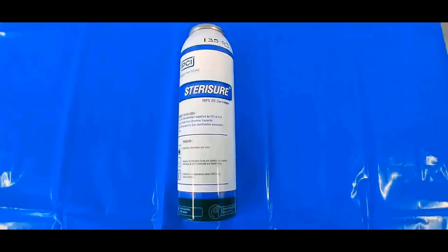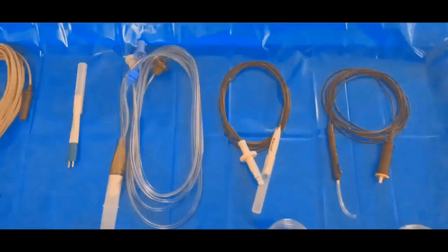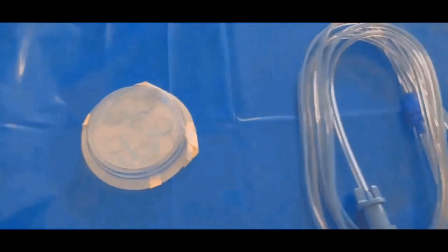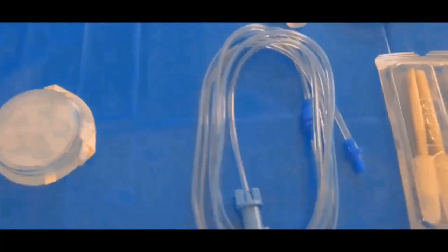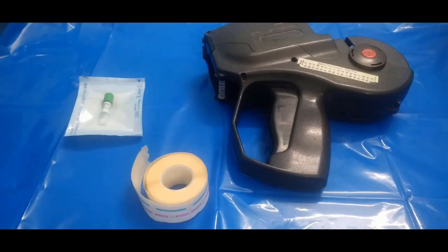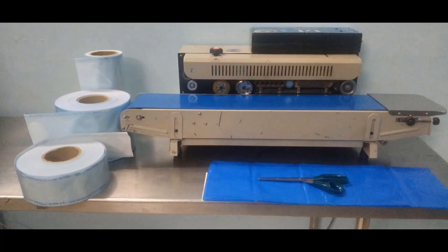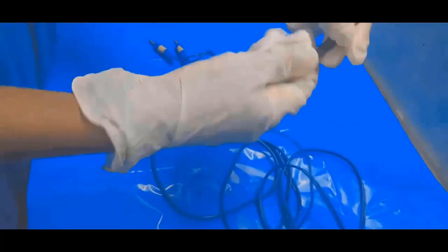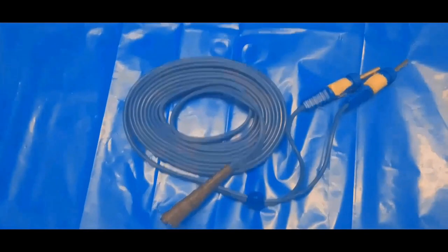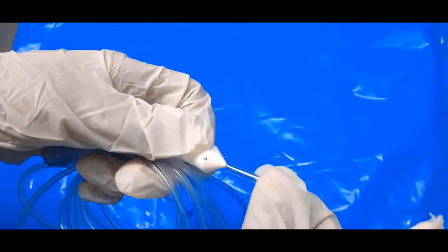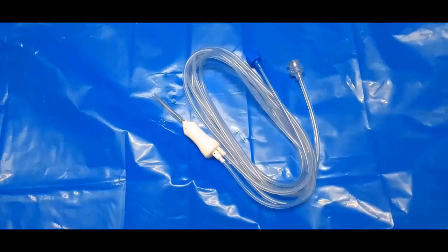Ethylene oxide cartridge. Things to be sterilized are cautery wire and tip, vitrectomy probe, light probe, iris hooks, retinal accessories and cotton pads. Class 1 indicator, 3-line label and gun machine. Biological indicator for ETO, sealing machine and medipeel paper, cutting machine or scissors. The above mentioned things are thoroughly cleaned in RO water before sterilization. Retina accessories are cleaned properly to remove any oil, as oil inhibits the penetration of ETO. The sharp tips are covered properly to avoid any breach in sterilization. The things should be properly dried before putting into the sterilization machine.